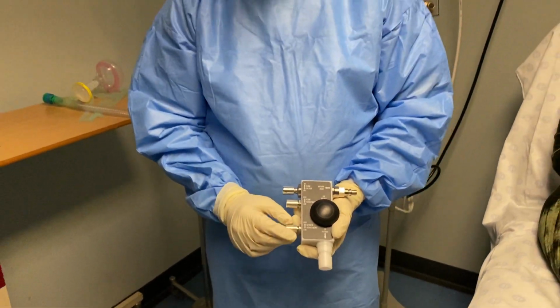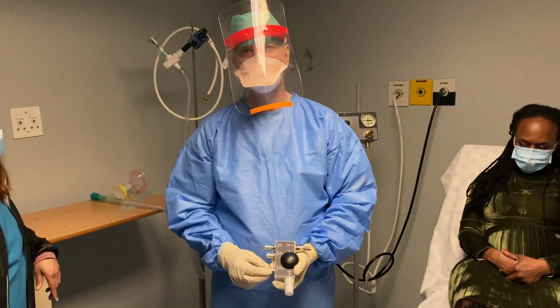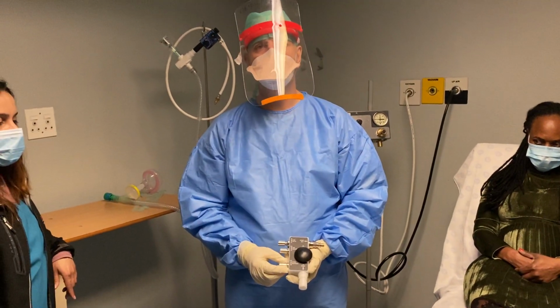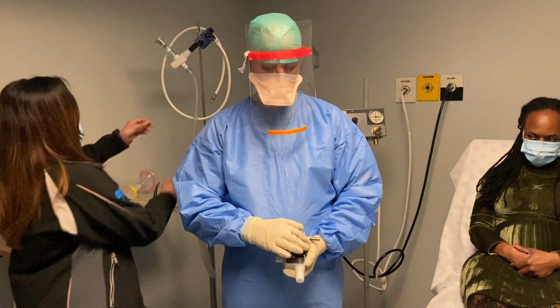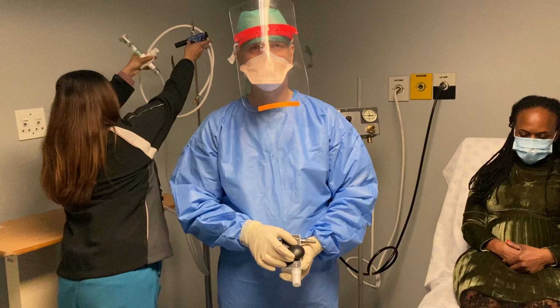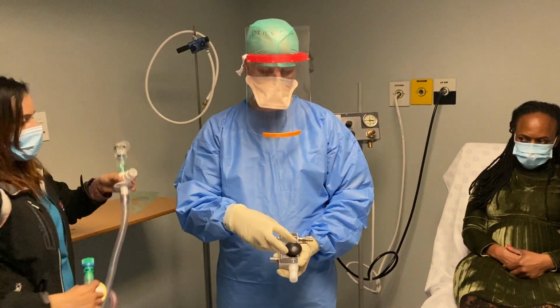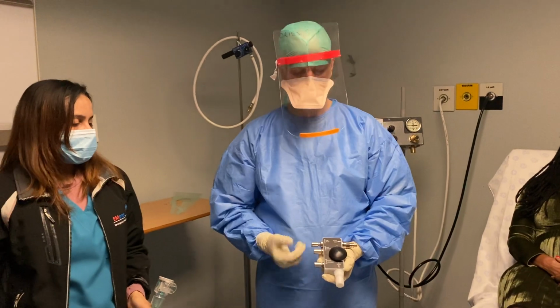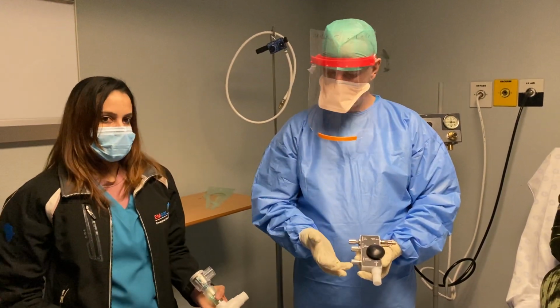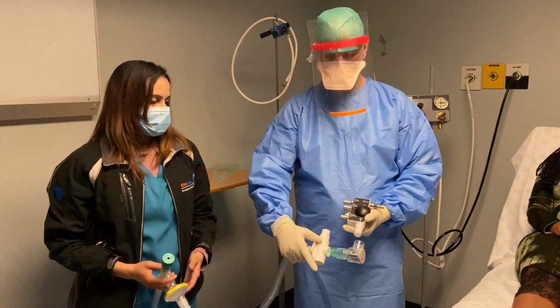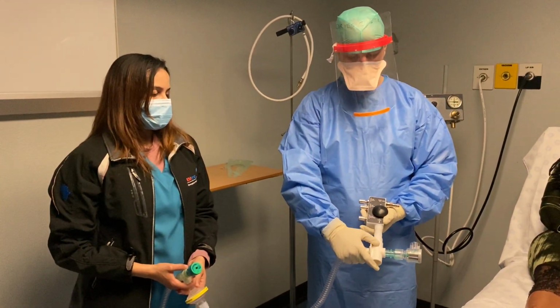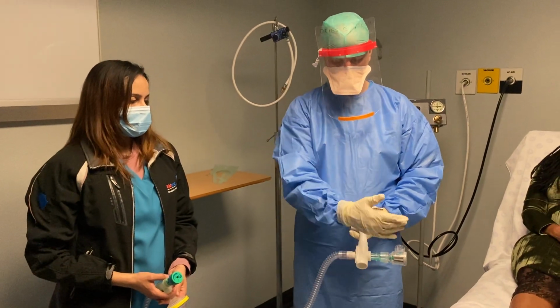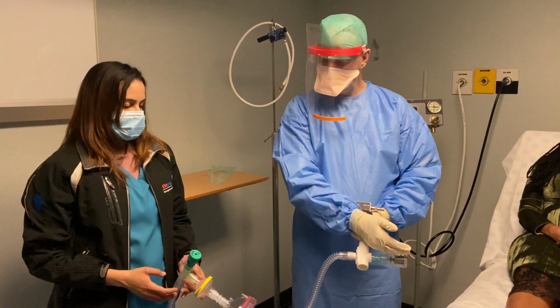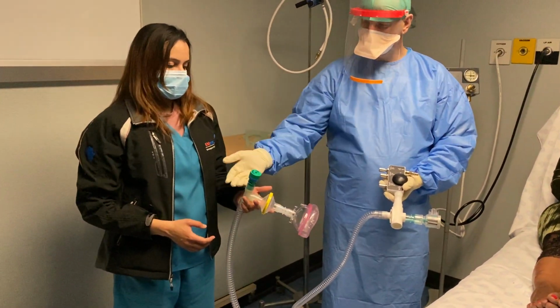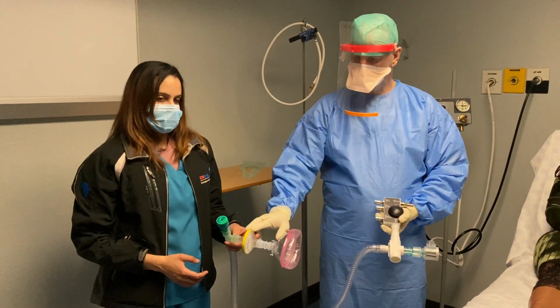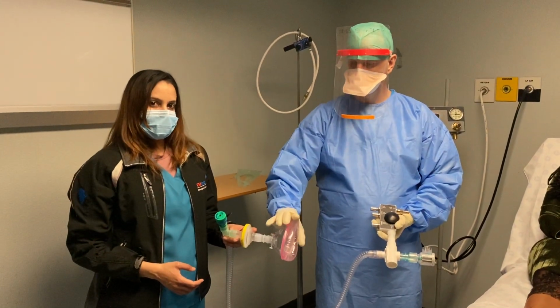concentration button. This button is not calibrated, so I'll simply be turning it up to administer a higher concentration of oxygen. This feature here is the entrainment valve, and this actually entrains room air into this device to administer to the patient. The device works with exactly the same circuit as the other 2 devices, and it simply is plugged into this port. And again, we've got our anti-asphyxia valve, our pop-off valve, our ventilation circuit, our T-piece, our PEEP valve, our viral filter, and the mask that applies to the patient.